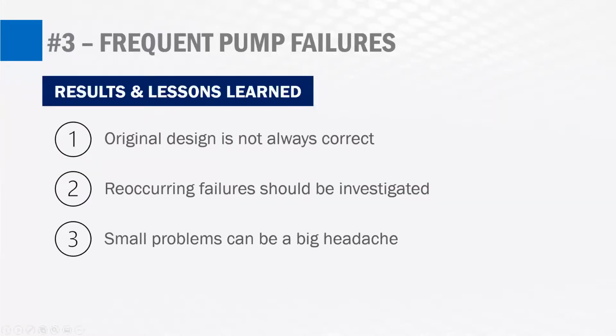So as a result, we learned that the original design is not always correct. We can't always assume that because that pump went through the design, the permitting and construction phases, it's always the right decision to just replace in kind or replace what was already there. Especially this is the case if that component is failing frequently or not living its full expected lifespan. Recurring failures definitely should be investigated.